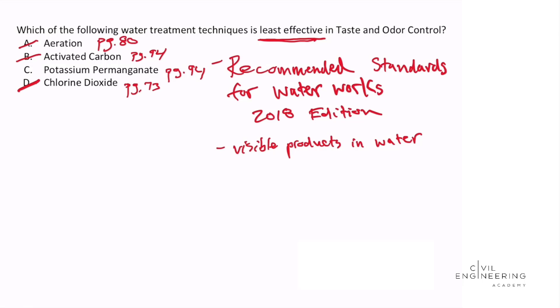Given my research through the Recommended Standards for Waterworks document, what stands out is that potassium permanganate leaves visible products in the water, which is not desirable for drinking water delivered to residents' homes and businesses. People don't want to see visible reaction products in water they drink, wash dishes with, or shower in. Using engineering judgment, answer choice C — potassium permanganate — is the least effective water treatment technique for controlling taste and odor.